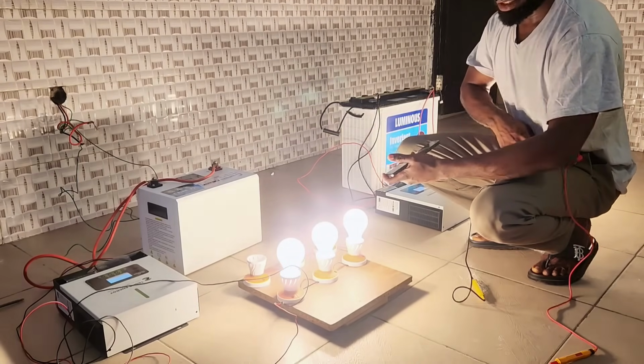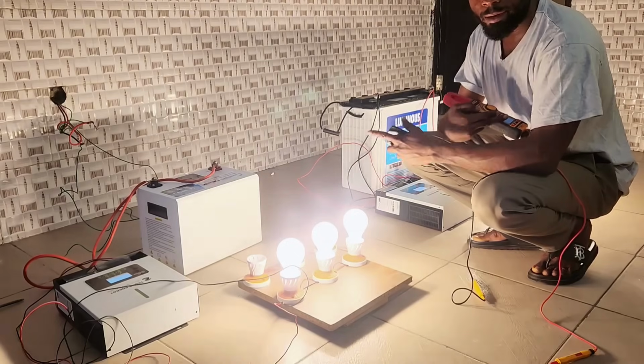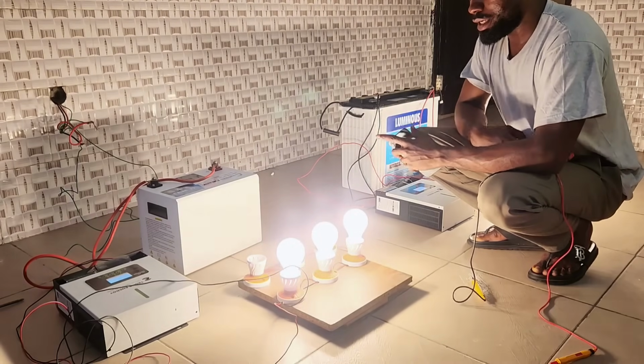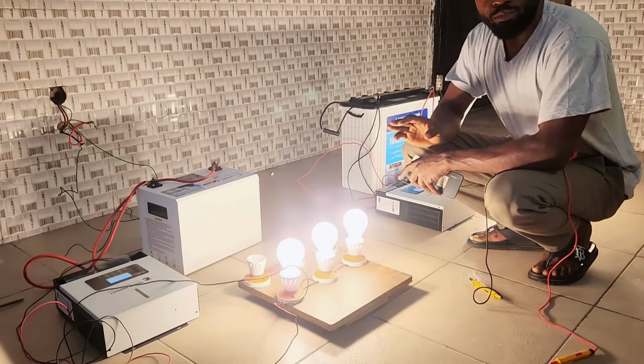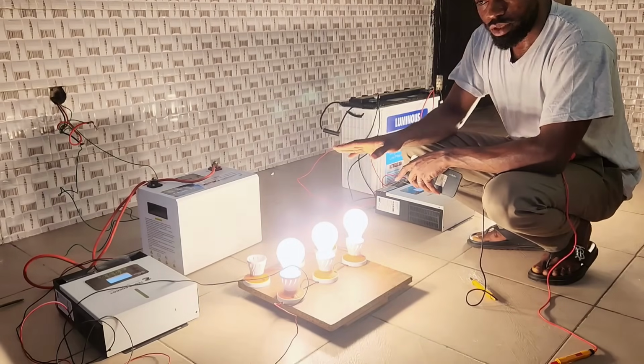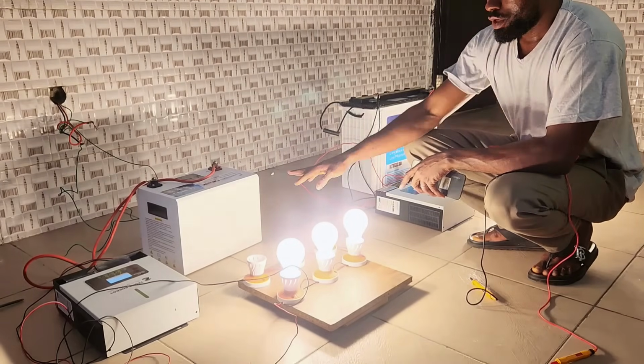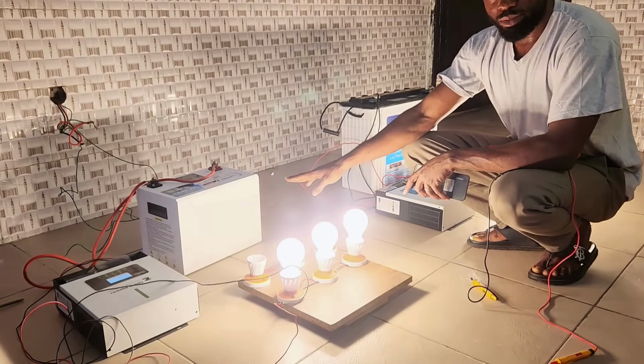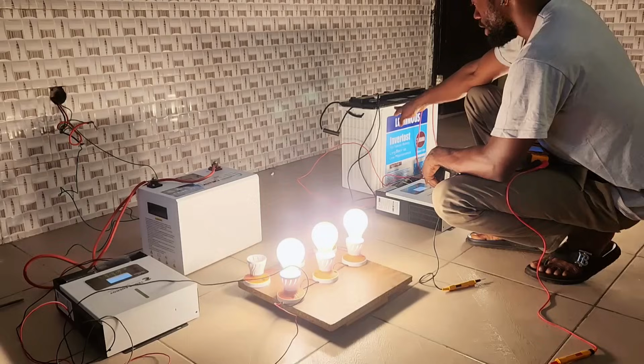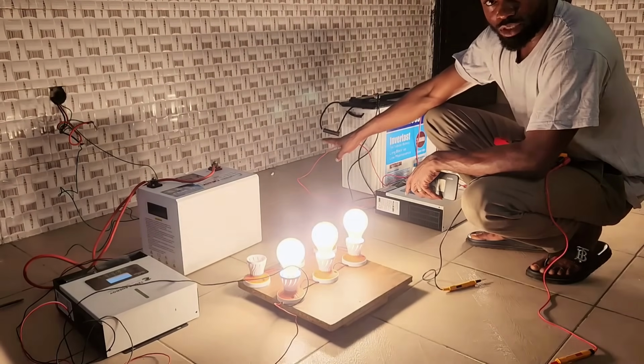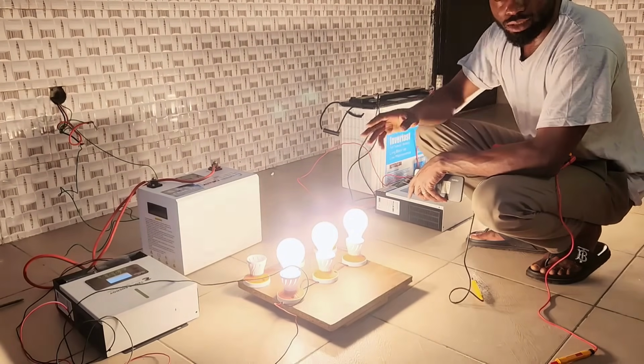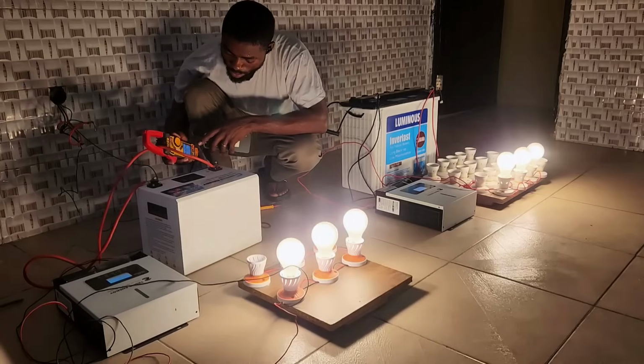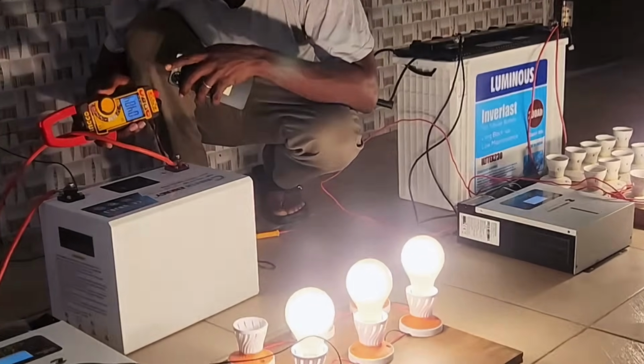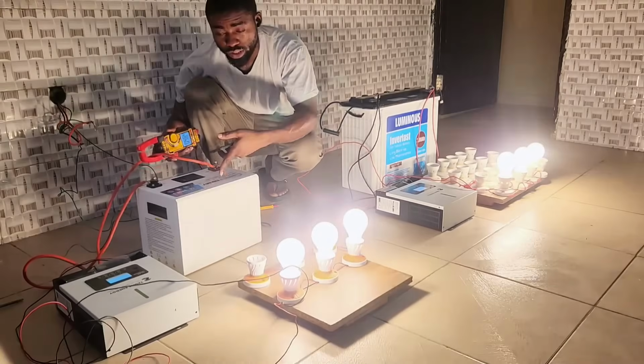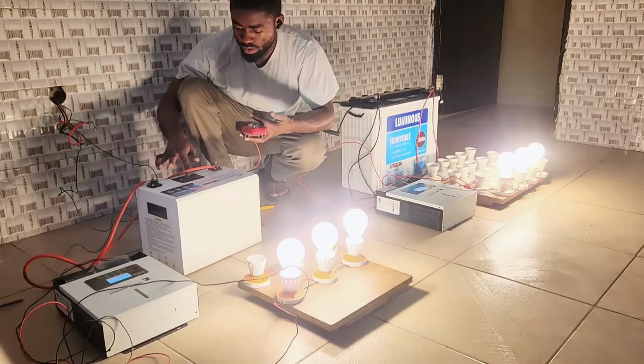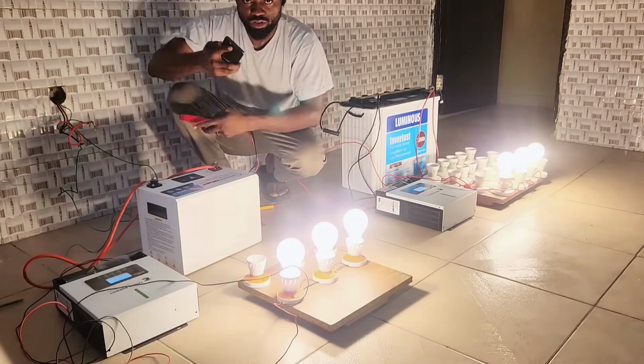Now we are going to use our digital multimeter to check what we are pulling from both batteries. And in this practical test, we are not following manufacturer's recommendation of draining this guy to 80%, and we are not following manufacturer's recommendation on this guy of 50% yield. So we are going to go above that or below that. Yes. So we are pulling about 48.4 amps from this very battery, which is a 100 amps lithium battery. Now, the voltage left in this battery is 12.6 volts.